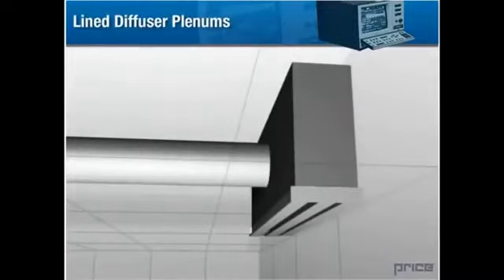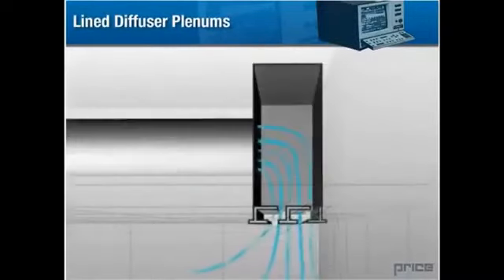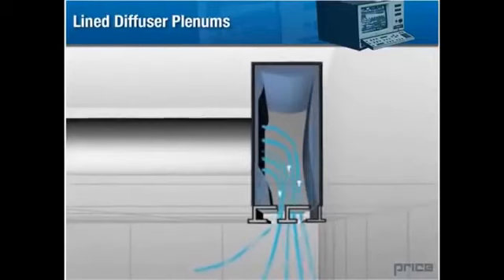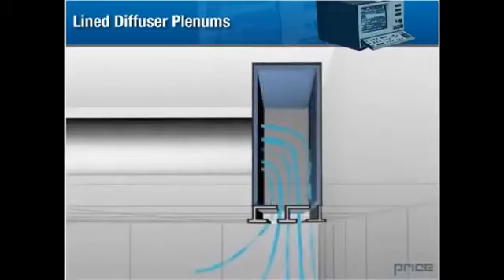Scenario 6. Lined diffuser plenums. Care must be taken when lining diffuser plenums. Excessive lining in a slot diffuser plenum can decrease volume, increase air velocity, and may actually introduce significant noise. Price manufactured plenums contain an optimal amount of lining so as to minimize the amount of noise produced.